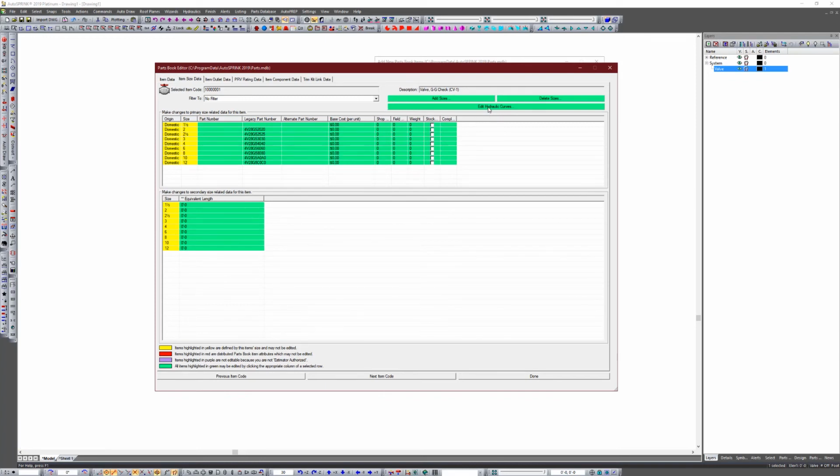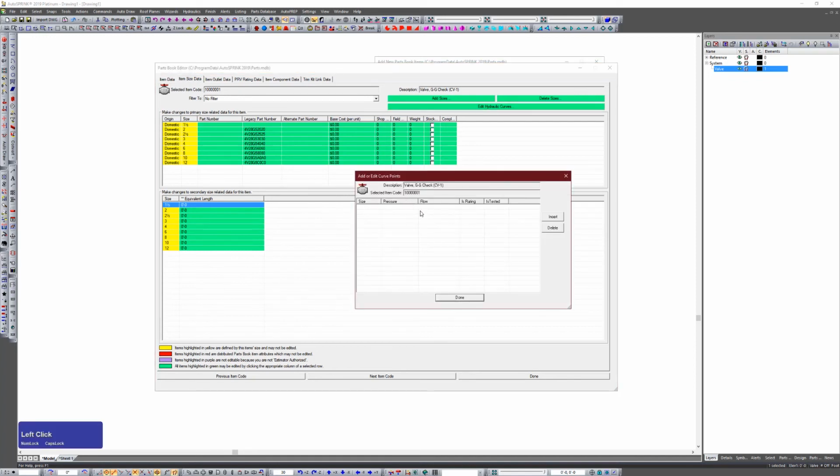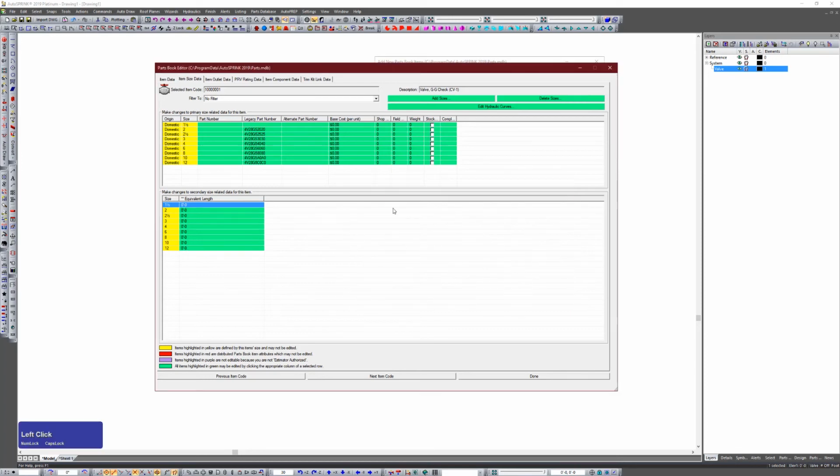This is where we also have the ability to edit hydraulic curves. I don't necessarily recommend using hydraulic curves for elements that aren't backflow preventers. I would much rather recommend using equivalent length values. The program is going to handle that better, and it's going to be a lot easier to enter this data. Editing a hydraulic curve, you have to enter multiple points and multiple sizes to develop a curve, and it's a lot more tedious to add these hydraulic curve points for each size than it is to just specify an equivalent length value for each size. But it is an option.